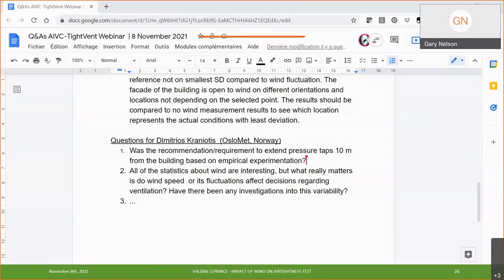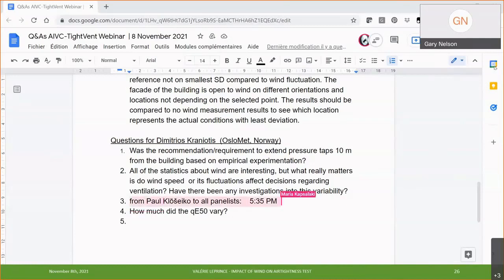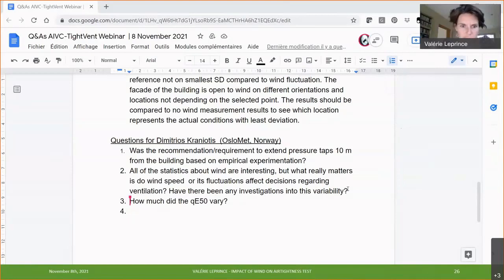And so if you then sense the outdoor pressure on the leeward side, you also have a negative wind pressure coefficient there. And so the two both go down together, and then maybe that's good because they cancel. But another house might have the leaks on the windward side, and it will be pressurized, and then it will actually be worse if you're measuring on the leeward side of the building. So I think it depends on the building a lot, and it would be important to test a bunch of real buildings. And I think nobody's done this. So we need another PhD for that, maybe. Yep.